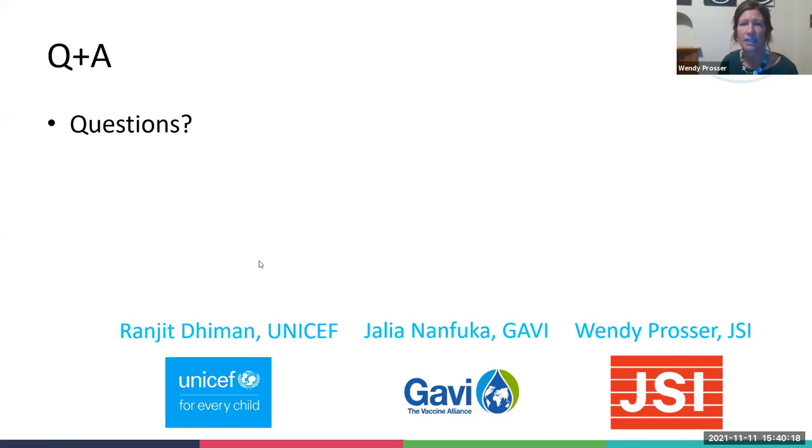There was a question on the temperature monitoring devices, if they have a certificate of calibration. Great question. When a device is PQS pre-qualified, it is certified for its life. All PQS temperature monitoring devices are certified for their life. So the new devices which have a life of 5 years or 3 years have a calibration guarantee for that period, and in case it is not, it is the responsibility of the field to bring that to the attention of PQS so that this can be addressed.